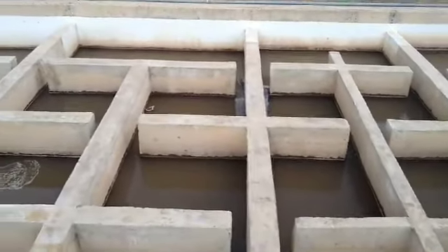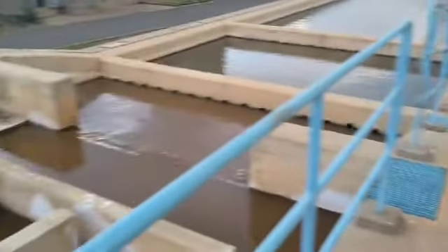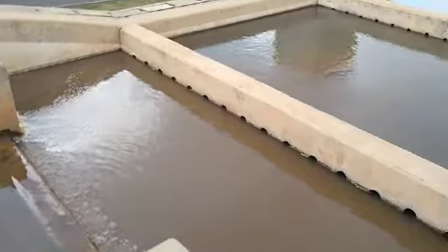For removal of suspended solids and turbidity, coagulation must take place. In our company, we use aluminum sulfate with positive charge, which is added to water to neutralize fine particles with negative electrical charge. When the charges are neutralized, particles come together forming soft, fluffy particles called flocks.